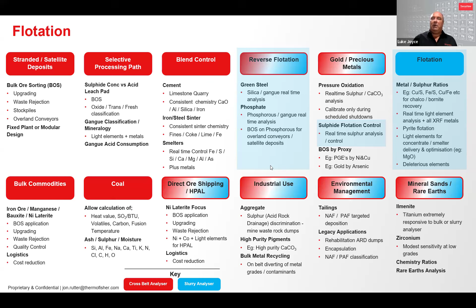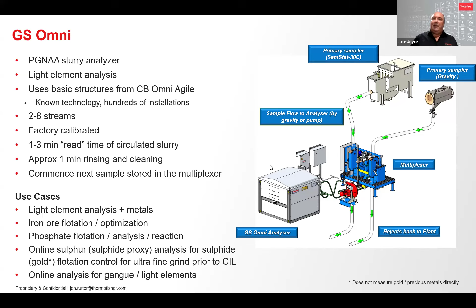So the GS Omni is a multi-stream PGNAA slurry analyzer, able to measure up to 8 streams. It uses the same proven technology as the cross-belt PGNAA analyzers, however, incorporates a multiplexer to sequentially measure sampled streams. Again, the differentiator between traditional online XRF slurry analysis being the ability to measure those lighter elements, and it's not limited by particle size.